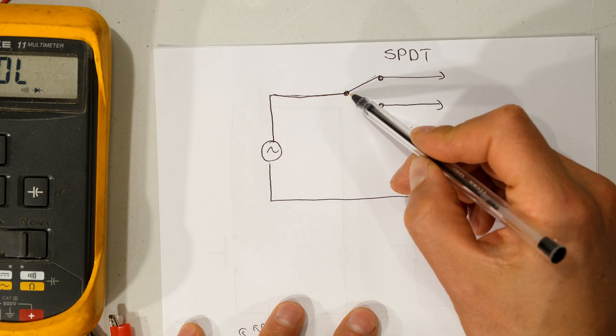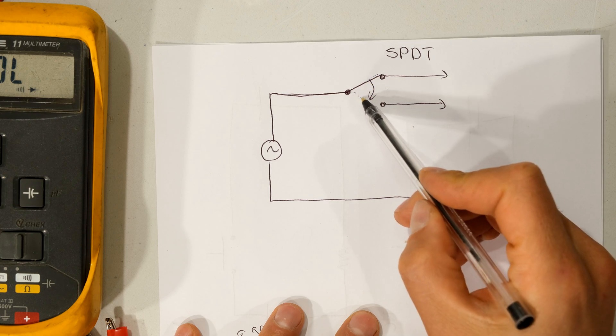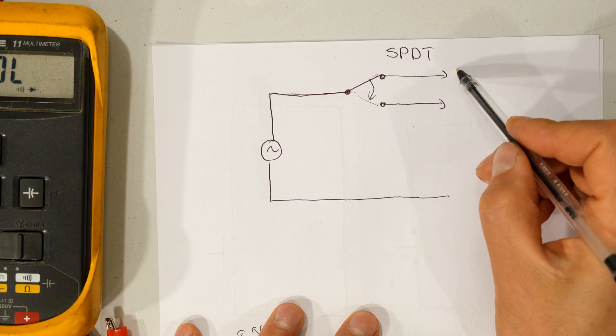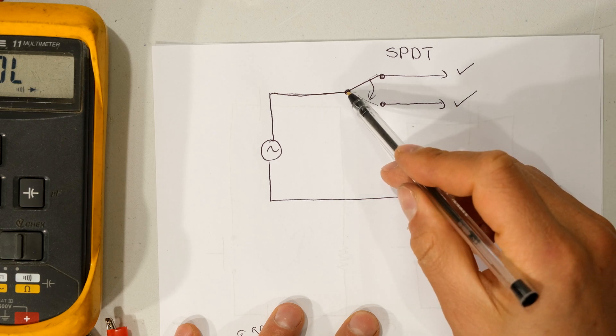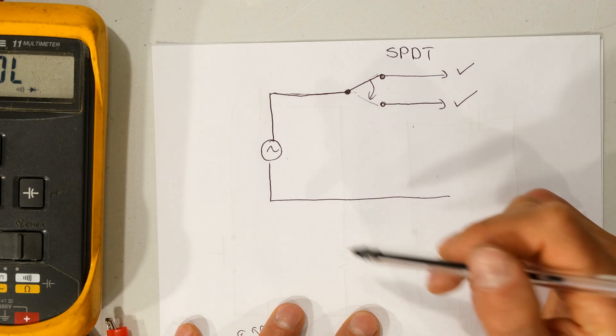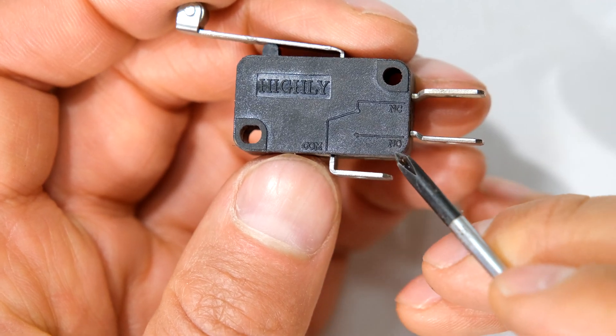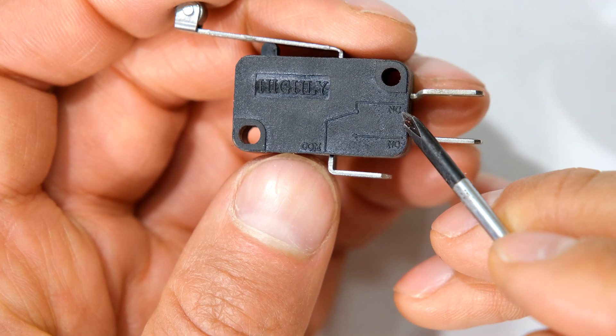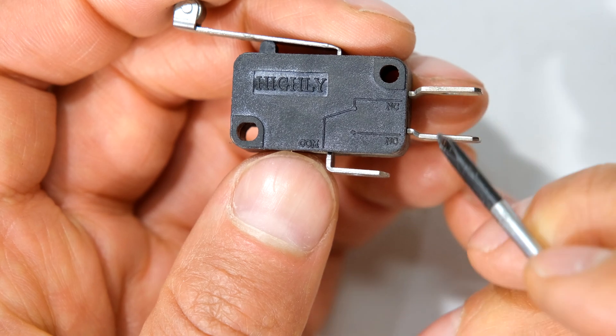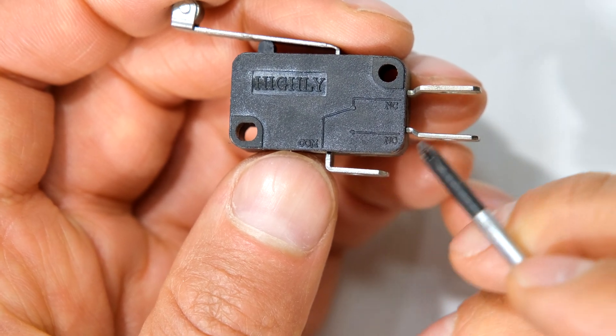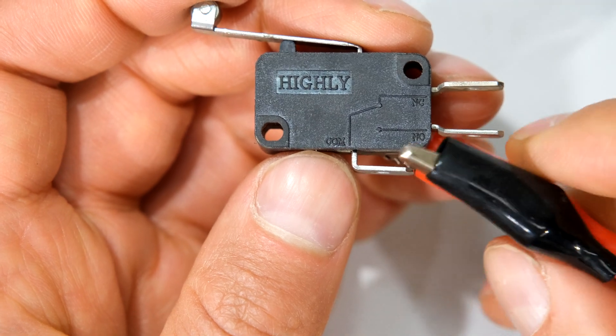Here's a quick diagram — there's a link that joins the common pole and it can move between two positions, allowing two different circuits to be connected to one supply. Over here I have a limit switch. On the front you can see it says common, NO, and NC — NC stands for normally closed and NO is normally open. So we also have three terminals here: one input and two outputs.